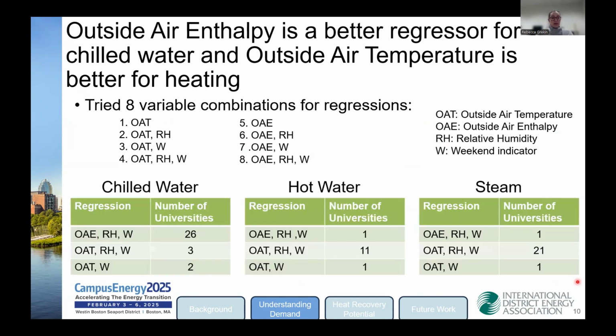What we see is that for chilled water, for 26 of the universities, the best regression is actually the one that gives the most amount of information - including both relative humidity and the weekend indicator, but with the base value being outside air enthalpy.